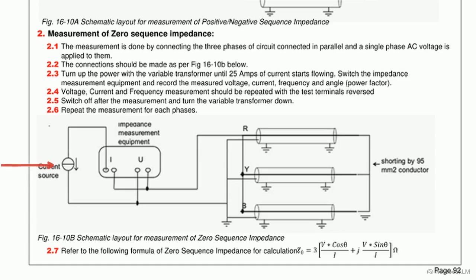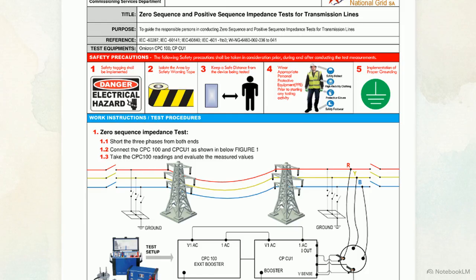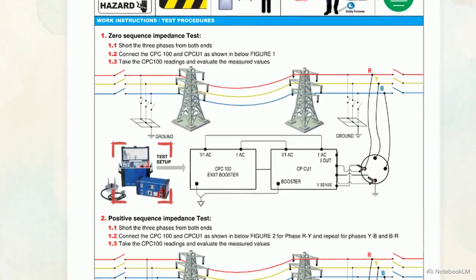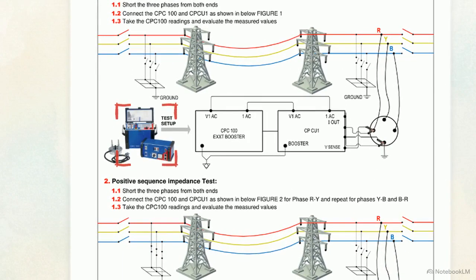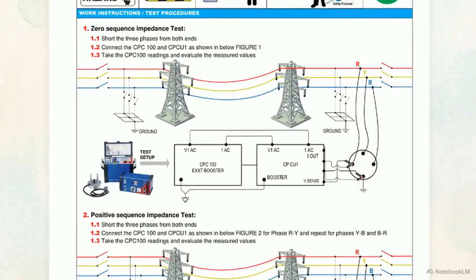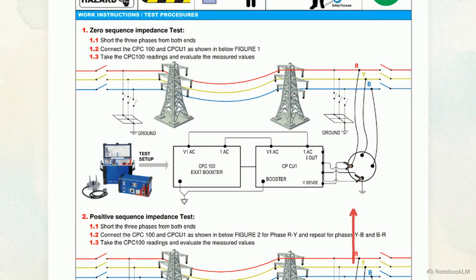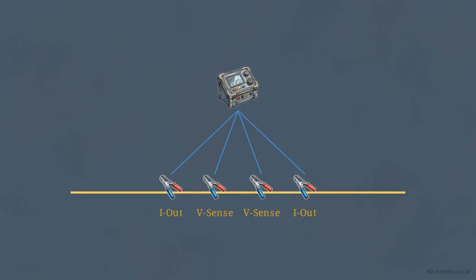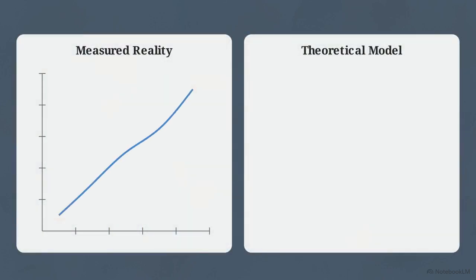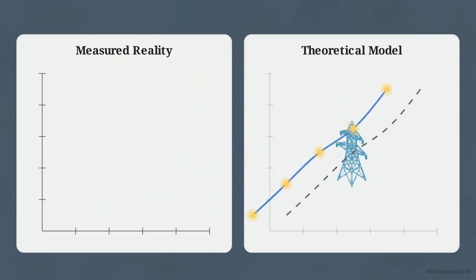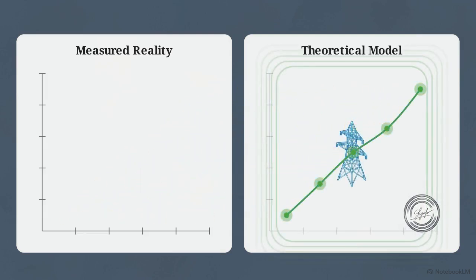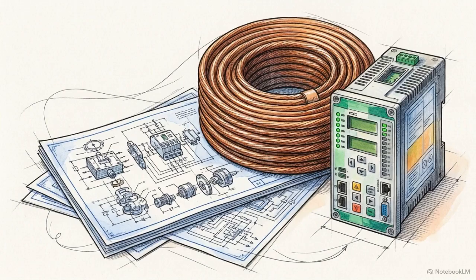This diagram details Test 13.12, extending sequence-impedance tests to the transmission lines using specialized equipment like the Omicron CPC100 and CPCU1 booster. To configure a zero-sequence test, the three phases must be physically shorted from both ends of the transmission line. Technicians configure the V-sense, I-out, and grounding leads, running the test injection to capture raw impedance values. These CPC100 readings are then aggressively cross-referenced against the theoretical, approved system study line model to validate accuracy. Accurate sequence impedance mapping acts as the final technical bridge. It confirms that the raw physical copper and aluminum architecture of the newly built grid behaves exactly as the computerized protection relays and network models expected it to.